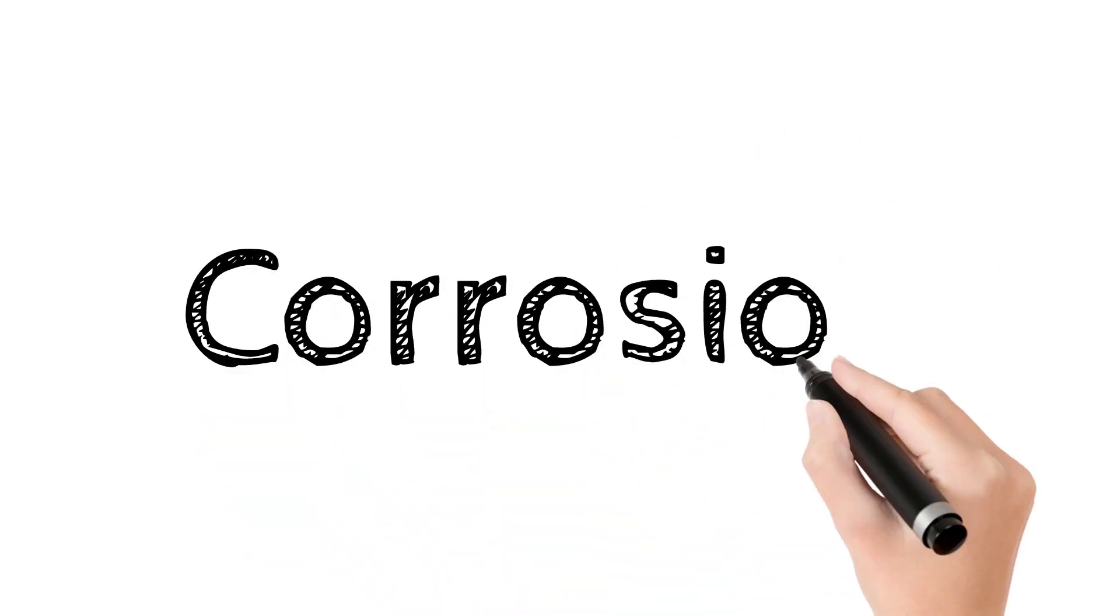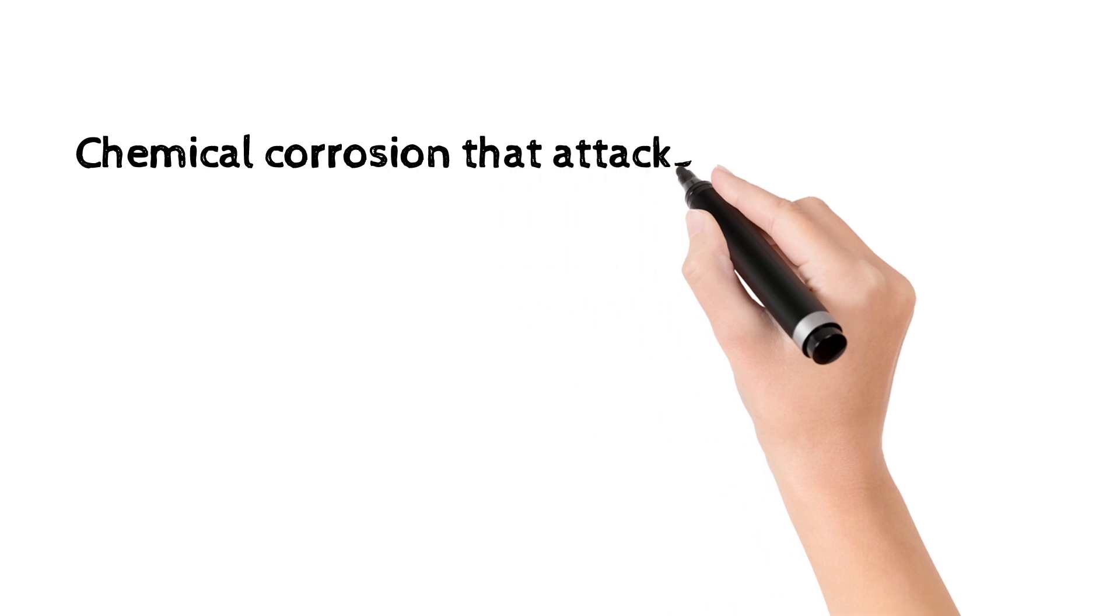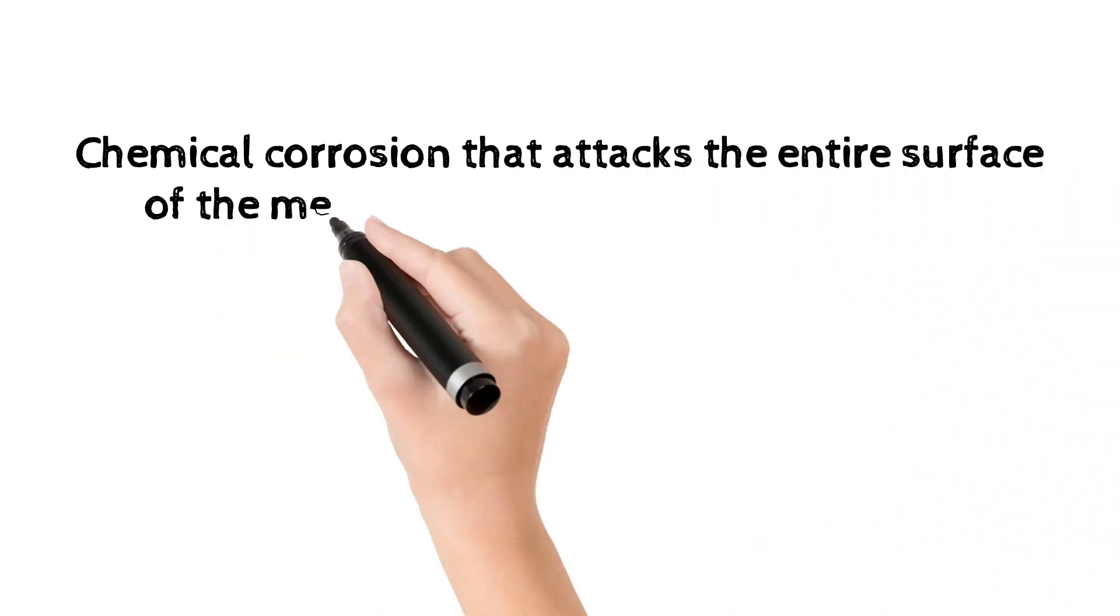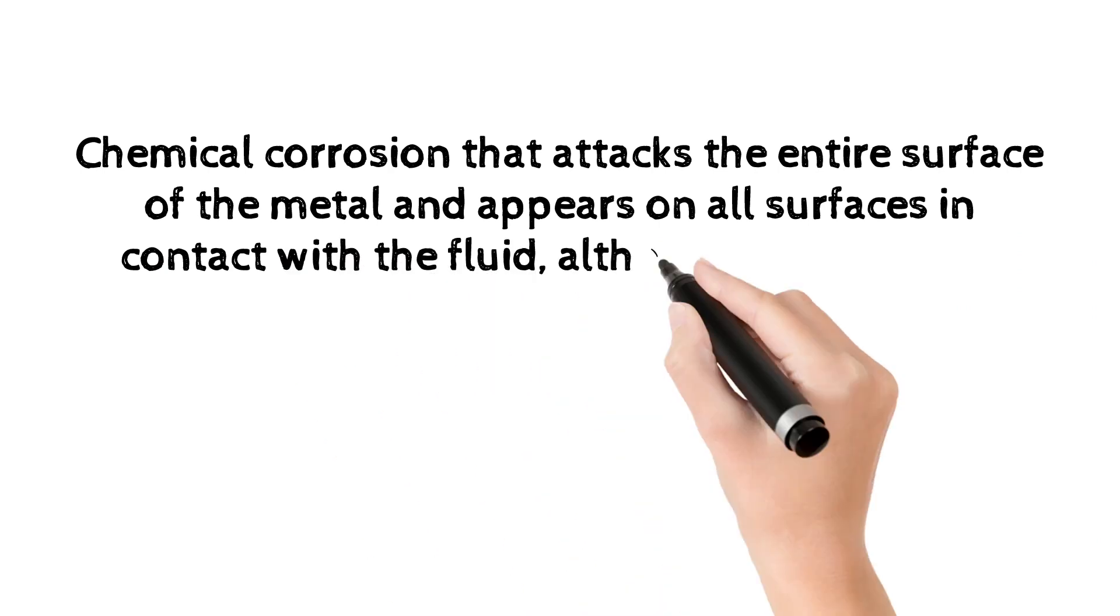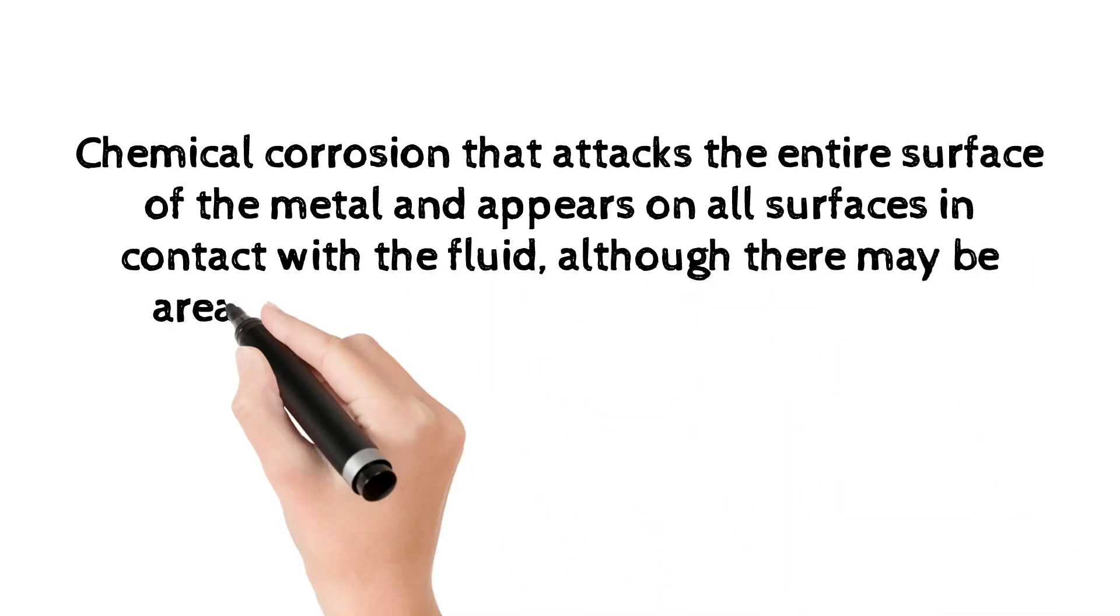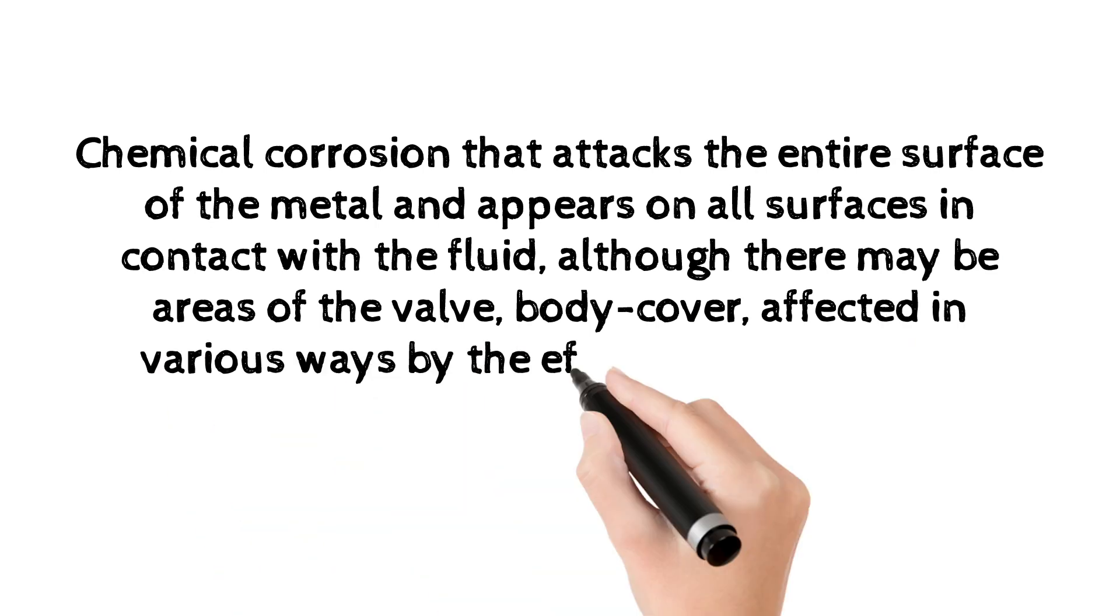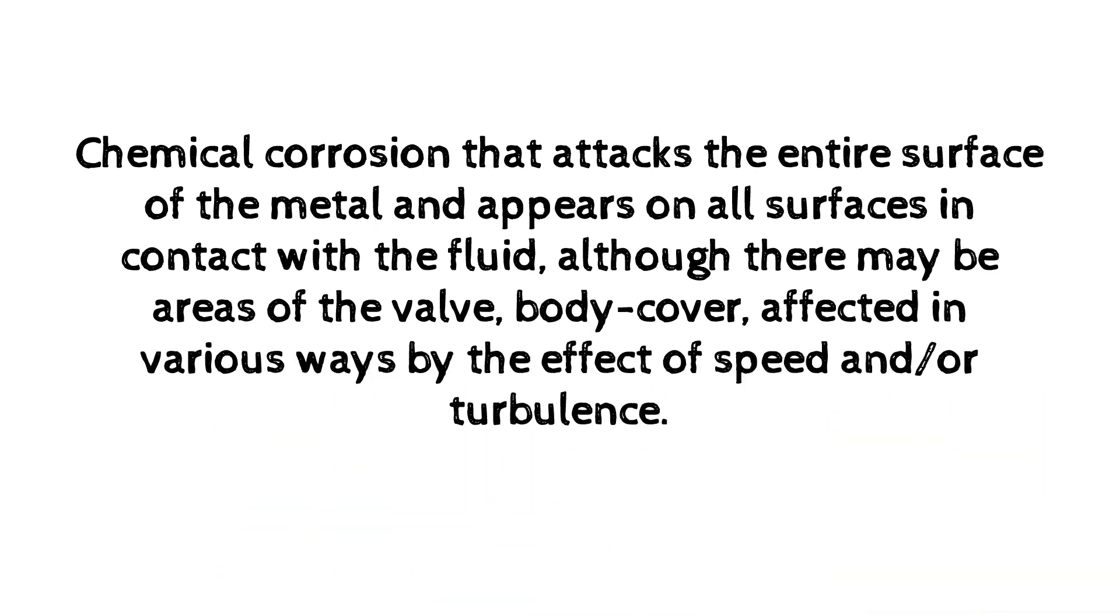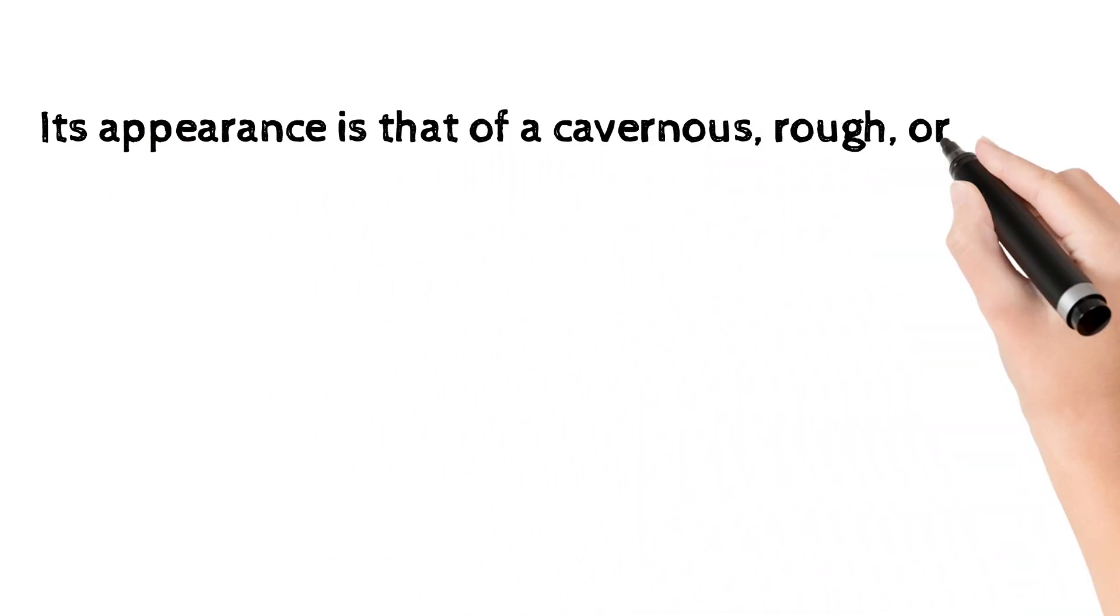Corrosion. Chemical corrosion that attacks the entire surface of the metal and appears on all surfaces in contact with the fluid, although there may be areas of the valve body cover affected in various ways by the effect of speed and or turbulence. Its appearance is that of a cavernous, rough, or pitted surface.